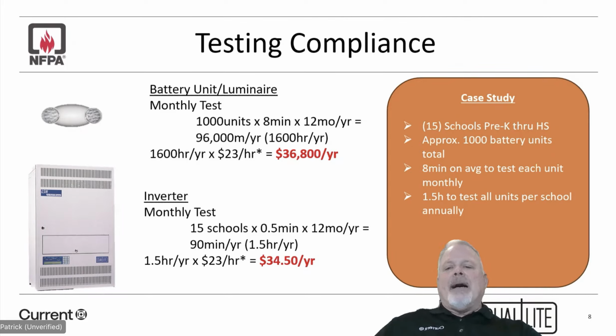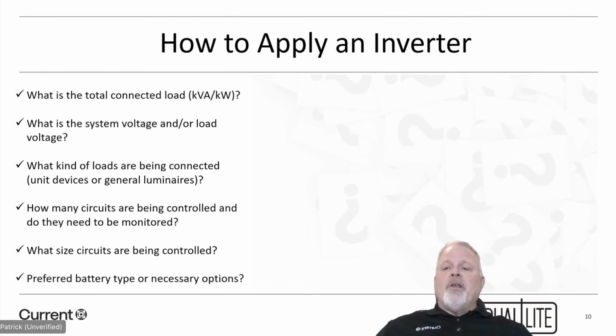$34.50. I would say anytime that you're looking at a job where you have 100 or more fixtures that need to be used or batteries that need to be used, the inverter should come into play and should take that into serious consideration. How to apply an inverter? When you look at the total connected load, what I often recommend to our partners is if someone comes to you and they say they have 2,000 watts for their total load, just to be on the safe side, I always recommend adding 25 to 35% to that. And that's the best way to size a unit on the fly. And you can be pretty confident that you'll be okay with that.